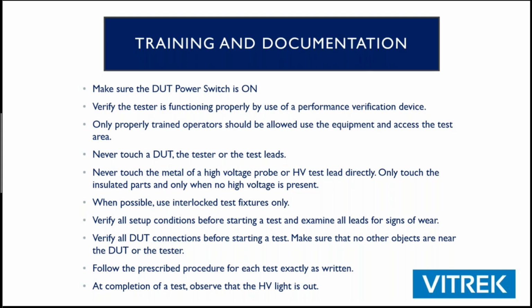It's very important to make sure that the tester is functioning properly. Most people are going to send their products in annually for calibration, and it's going to be verified that they are outputting the proper voltage and able to measure current. What if your product happened to break on shipping, being returned from your calibration lab, and you went ahead and tested products for a whole year and thought everything was great and you were passing, but you weren't outputting? There could be a situation where a failure like that could occur, and that's why we want to do a more frequent verification, which we'll talk about a little bit later.